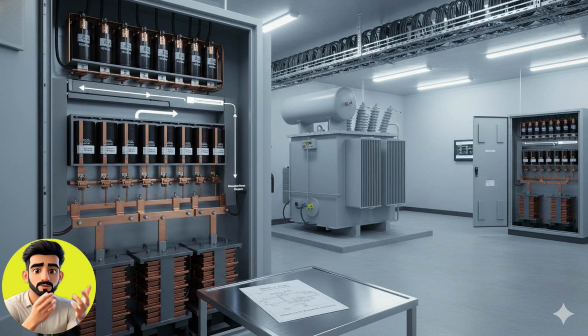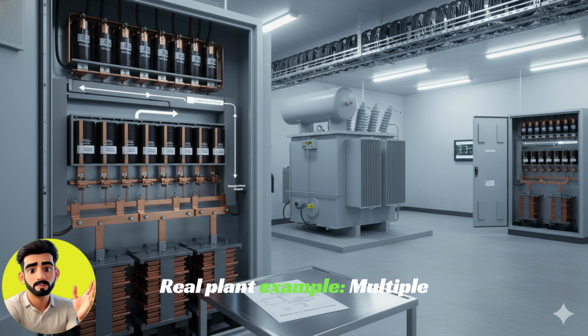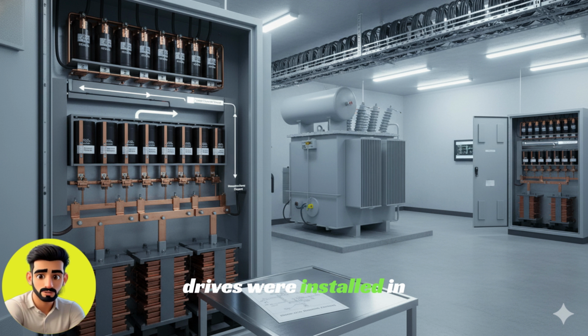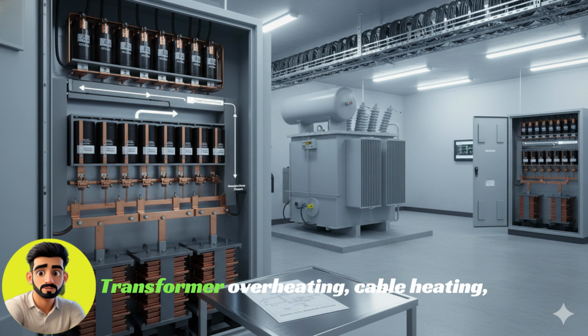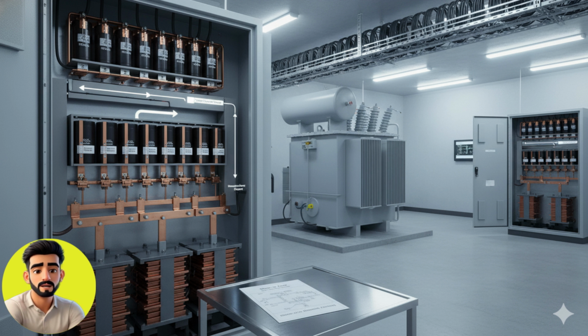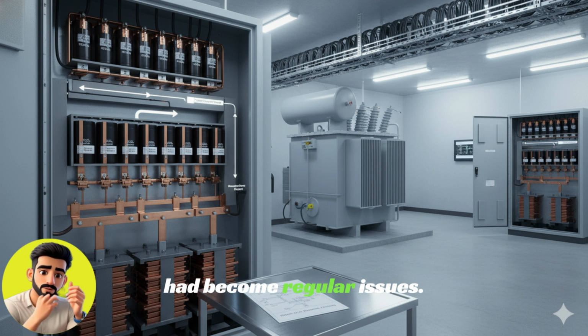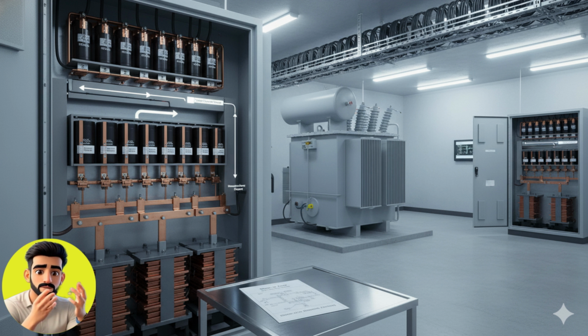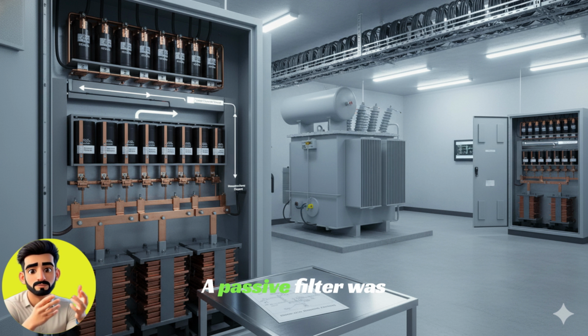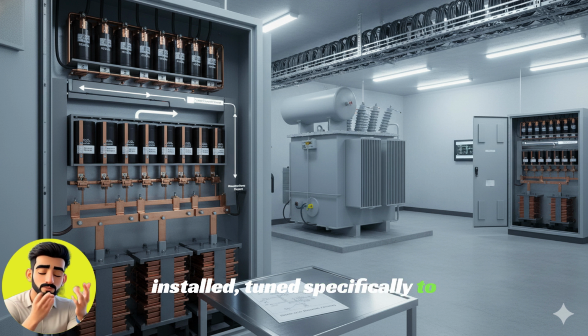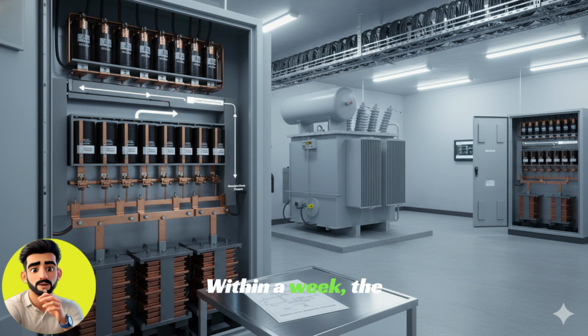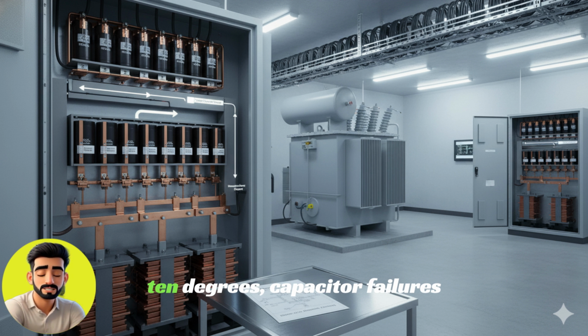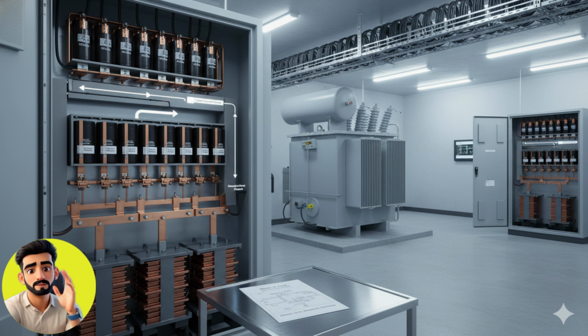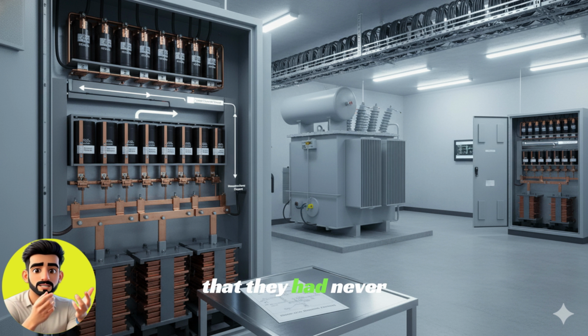Real plant example. Multiple drives were installed in a food processing plant. Transformer overheating, cable heating, and capacitor bank failure had become regular issues. A passive filter was installed, tuned specifically to the fifth harmonic. Within a week, the transformer temperature decreased by 10 degrees. Capacitor failures stopped completely, and drive trips ceased. The plant team reported that they had never seen such clean power quality before.